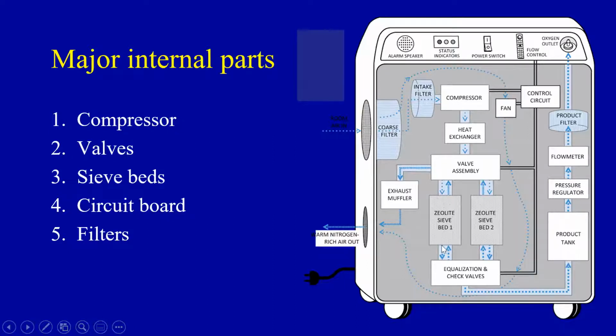That removes the nitrogen, and then it goes through what's called some other valves, and into what's called a product tank, which is really just an oxygen tank within it. Then there's a pressure regulator, which regulates the amount of pressure and flow. Then it goes through the last filter and comes out and can go to the patient.